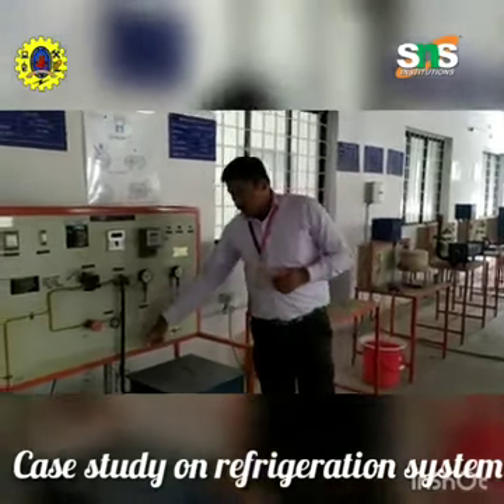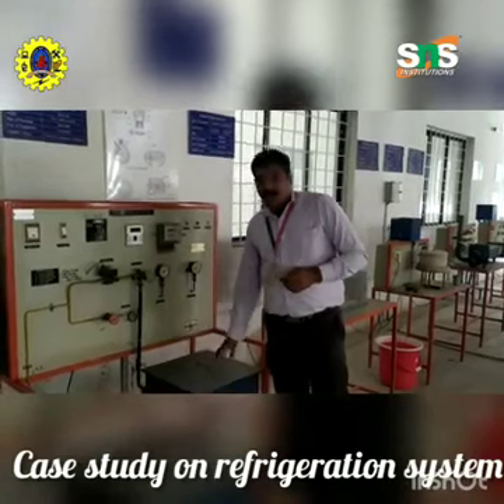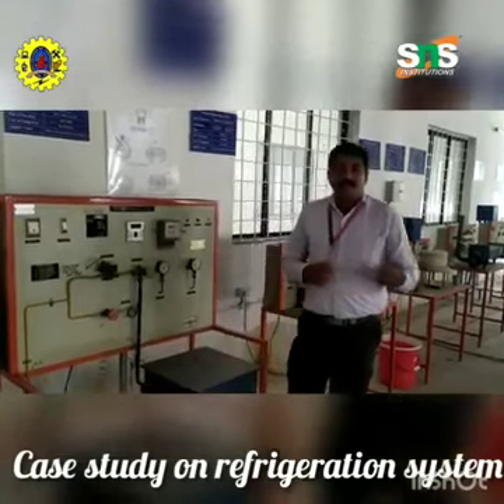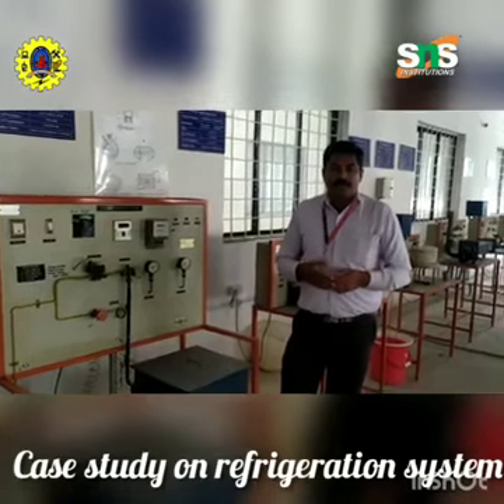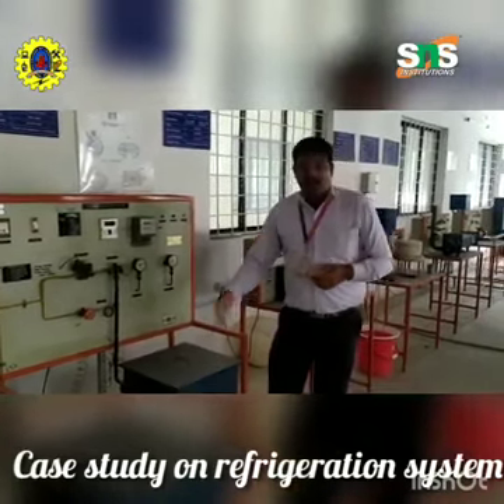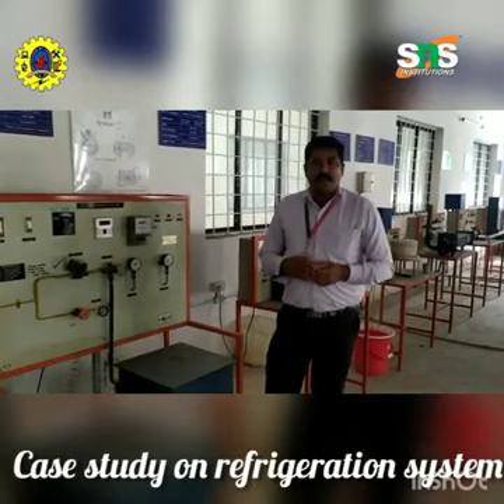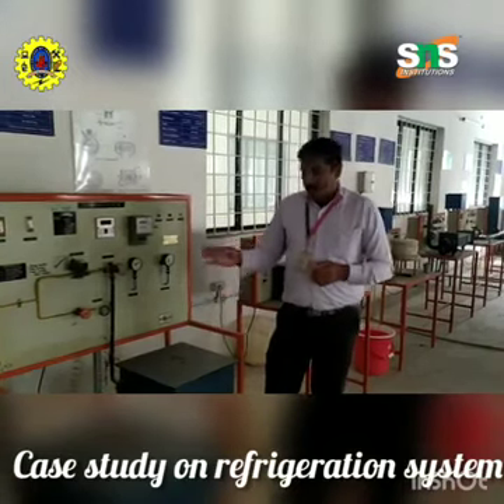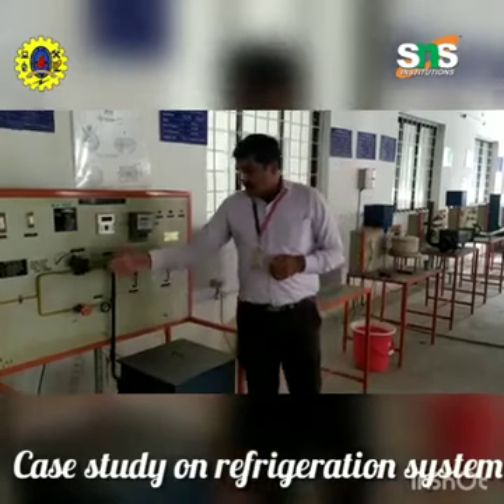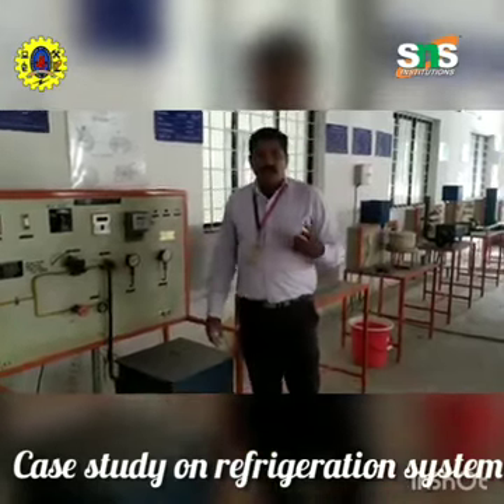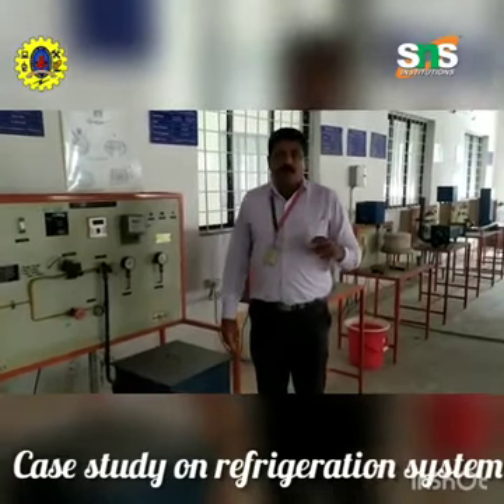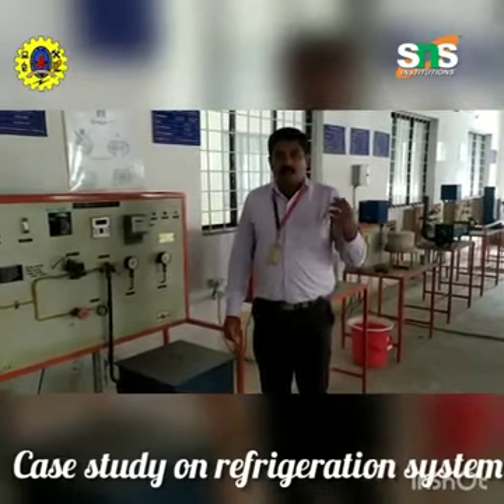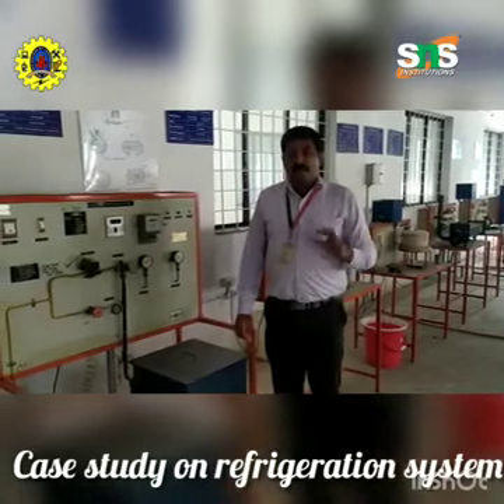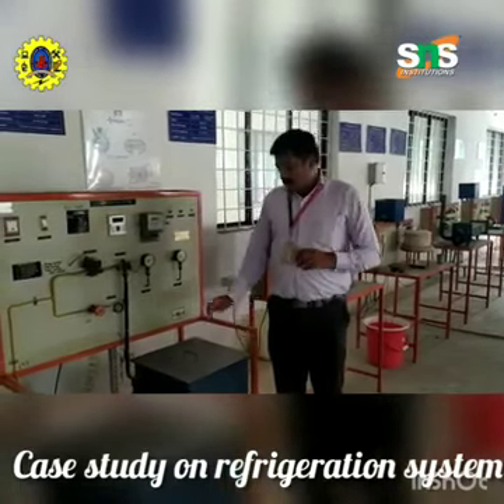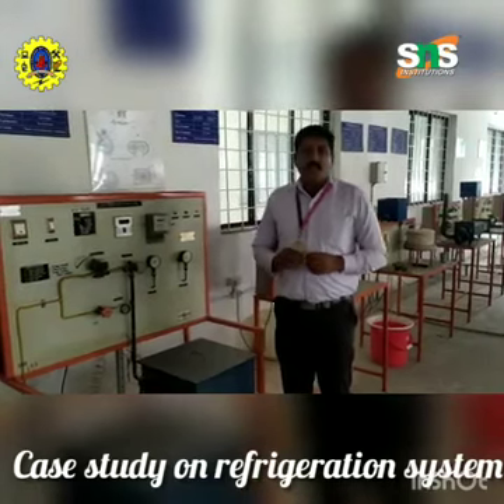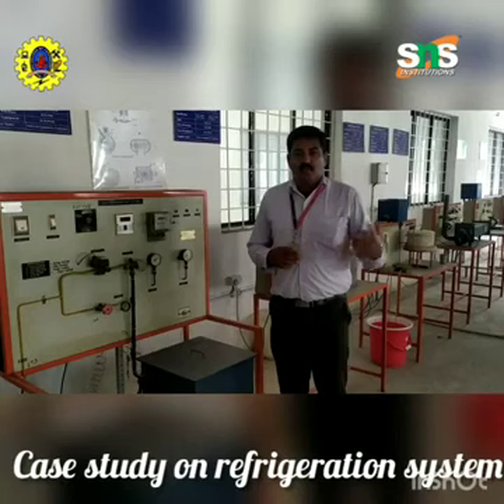When the liquid refrigerant enters the evaporator, it absorbs the heat and is converted into vapor. This vapor comes to the compressor, which pumps the gas towards the condenser. In the condenser, it is cooled down, and the pressure is increased because of the compressor, but the state is changed. The gaseous state is converted into liquid state in the condenser by rejecting the heat to the atmosphere.